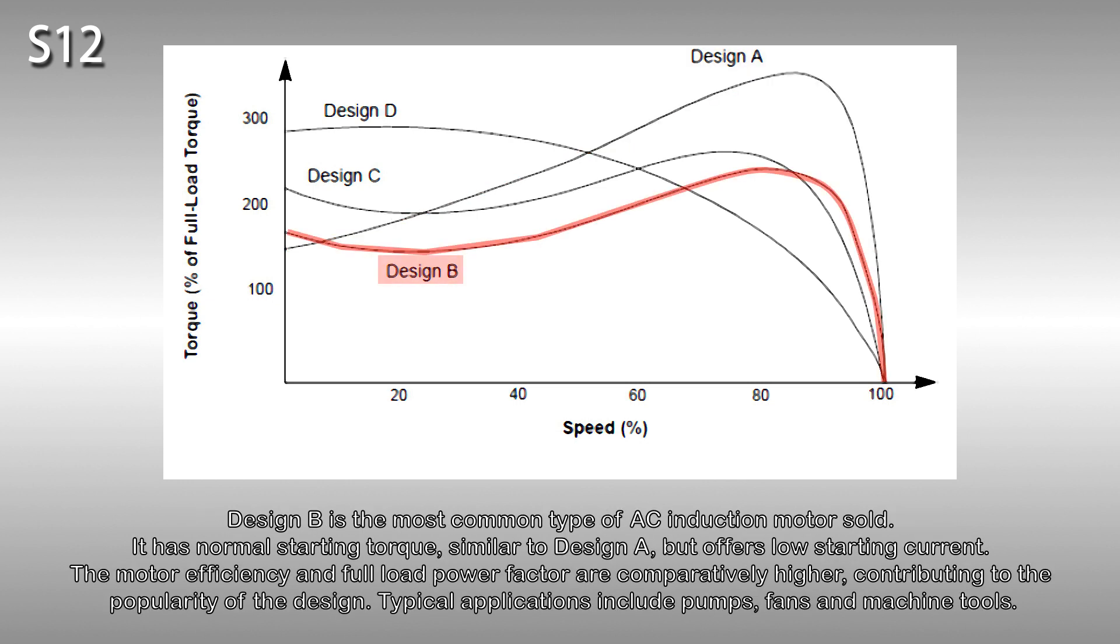Design B is the most common type of AC induction motor sold. It has normal starting torque, similar to design A, but offers low starting current. The motor efficiency and full load power factor are comparatively higher, contributing to the popularity of the design. Typical applications include pumps, fans and machine tools.